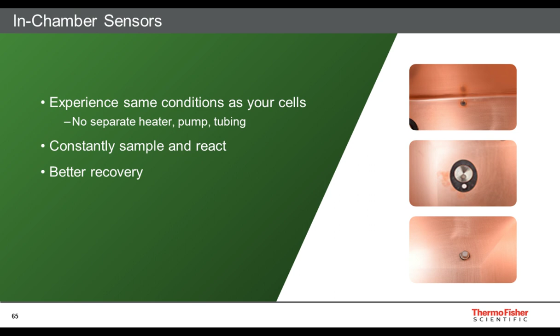In other words, inside the incubator chamber, you need very solid state, very robust components to withstand those conditions. But the important thing is that if you're using a sensor to control the conditions that the cells are experiencing, then you want the sensor to experience the same conditions that the cells are experiencing, and that just can't happen with a bypass sensor. So look for an incubator with sensors in the incubator chamber that experience the same conditions as your cells and don't require additional equipment in an external space. This allows those sensors and probes to constantly sample and react to the conditions in the incubator chamber, and that will give you faster recovery after a door opening.